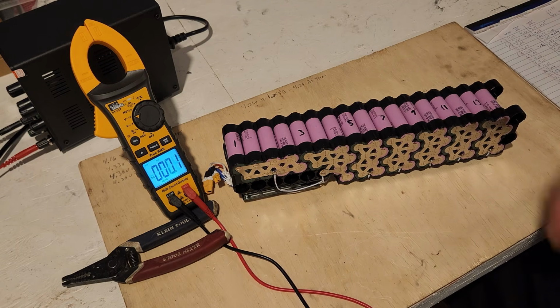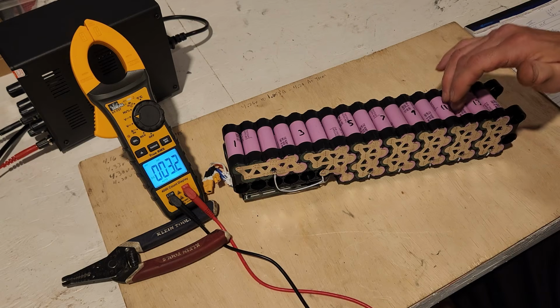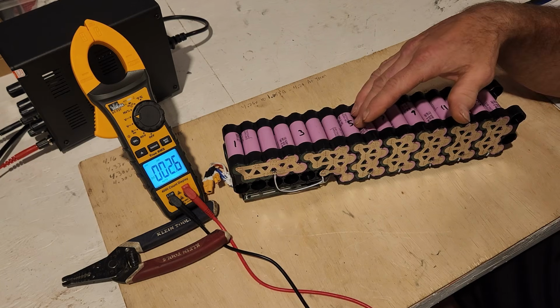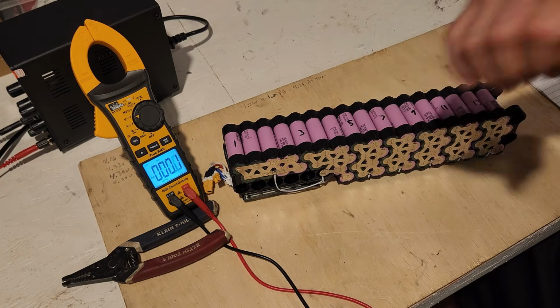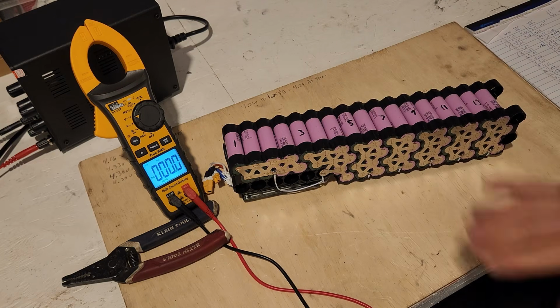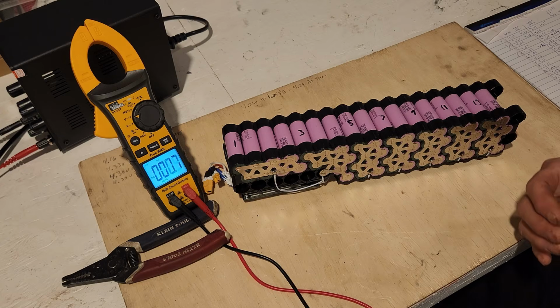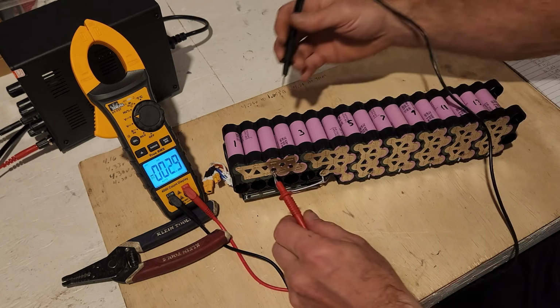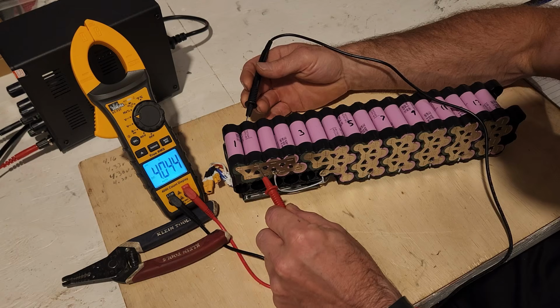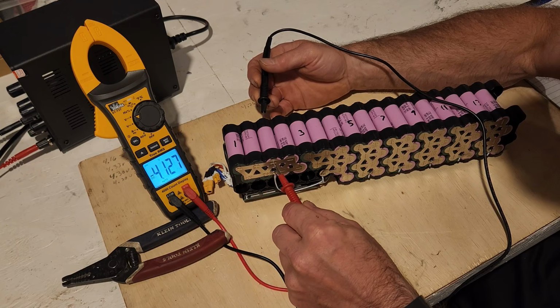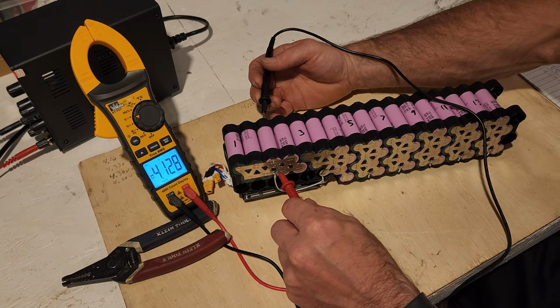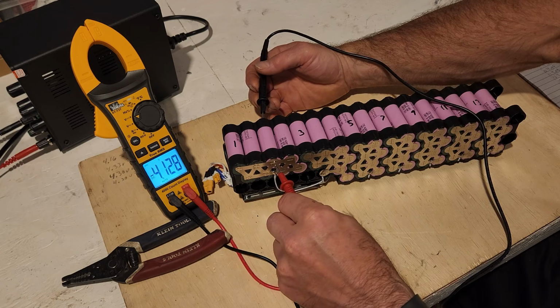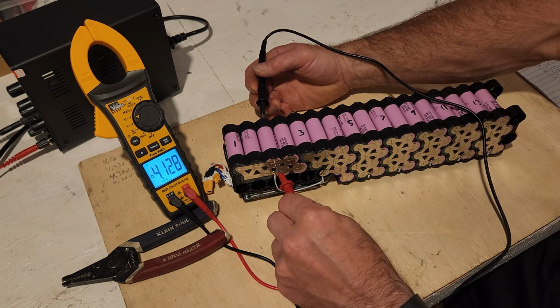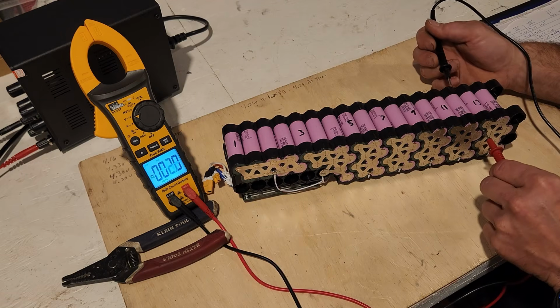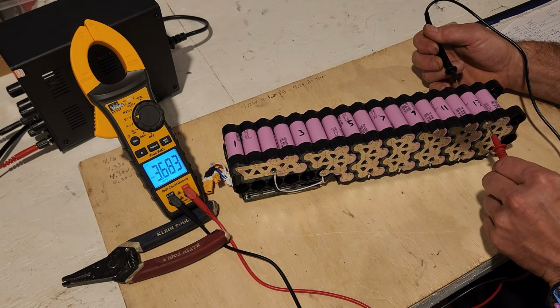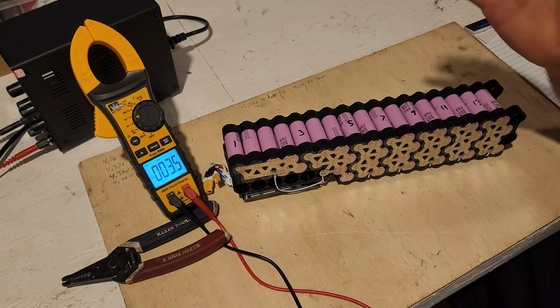So obviously when this is cutting down, all it takes is one of these cells to hit below 3.2 volts to cut that BMS, to cut the power off. That way you don't drop it too low. Same thing on the charging - like I had a 4.12. Yeah, 4.12, so that is group 2, 4.12, almost 4.13 volts. And then all the way down to my lowest, 3.68. So you see how far out they are?